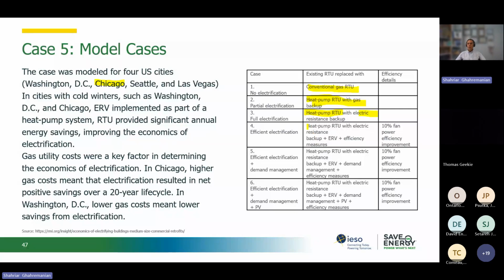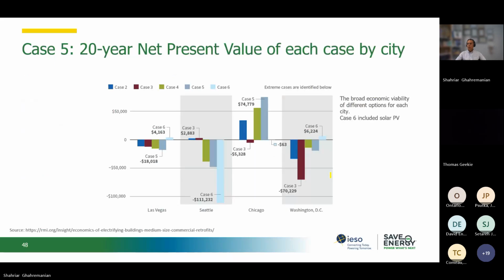And then option four is the heat pump rooftop unit with electric resistance backup plus the energy recovery and some other efficiency measures and so on. So for options 4, 5, 6, they consider the same heat pump with electric backup for extreme conditions, but they added more energy efficiency measures to the facility as well. If you look at it, each color shows different cases. For example, cases 4, 5, 6 that we look at all have a heat pump with electric resistance backup. And you see that all of them bring savings to the building owner.